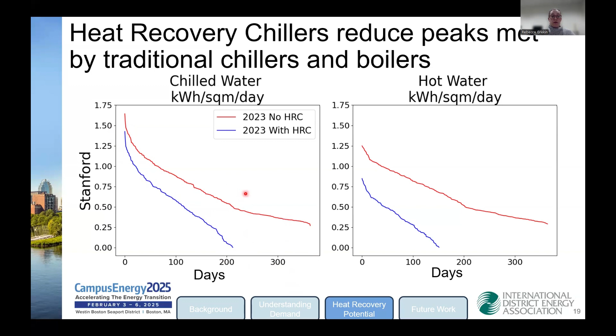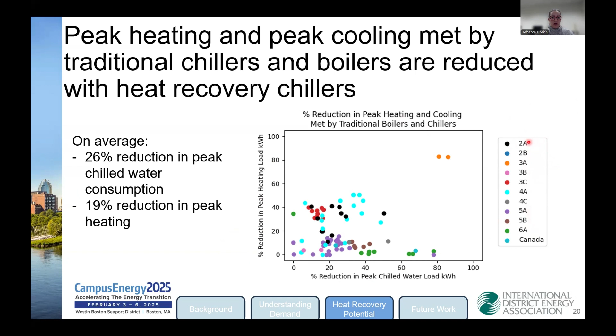Here we can also think about the peak heating and cooling. The percentage of the peak heating and cooling which is met by traditional chillers and boilers can be significantly reduced when you implement a heat recovery chiller. Here we have the percent reduction in peak heating load and the percent reduction in peak chilled water load. This is how much your traditional boilers and chillers do not need to produce because your heat recovery chiller is producing. On average, we saw a 26% reduction in peak chilled water consumption and about a 19% reduction in peak heating. Again, these are colored by climate zone, where 2 is hot, and A is humid, B is dry, and C is marine. And then the numbers go from hot to colder.